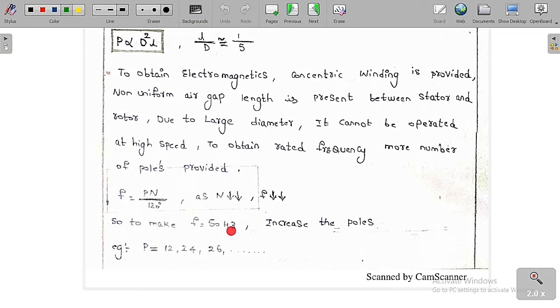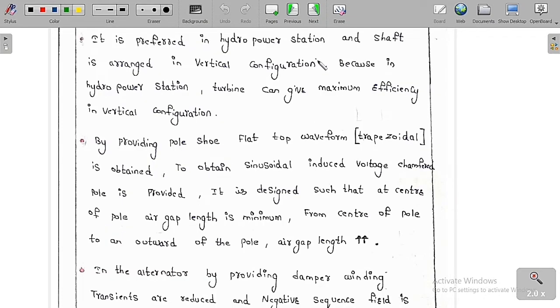So to make F equal to 50 Hz, increase the number of poles. The minimum number of poles which you can see in a practical salient pole alternator is always 12. You cannot see less than 12. The minimum value is 12, and only more than that you can see in the general case in the world. So the minimum number of poles of a salient pole alternator is always 12. You cannot see less than that. This salient pole alternator is always used in the hydropower station, and the shaft is arranged in vertical configuration.